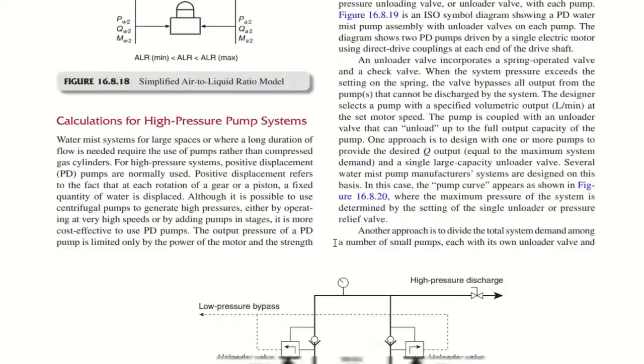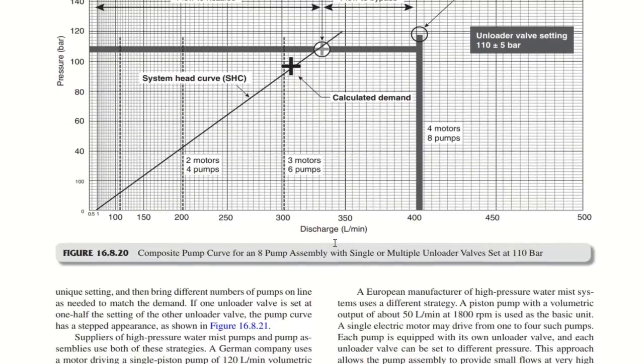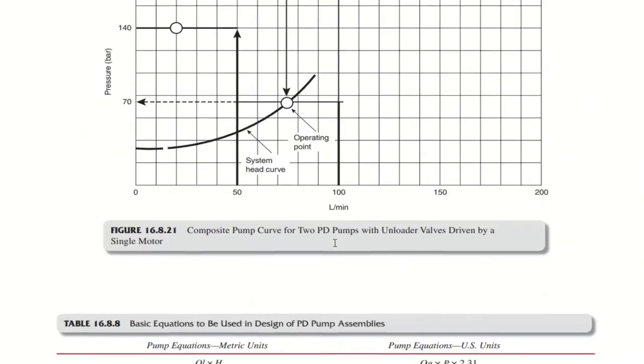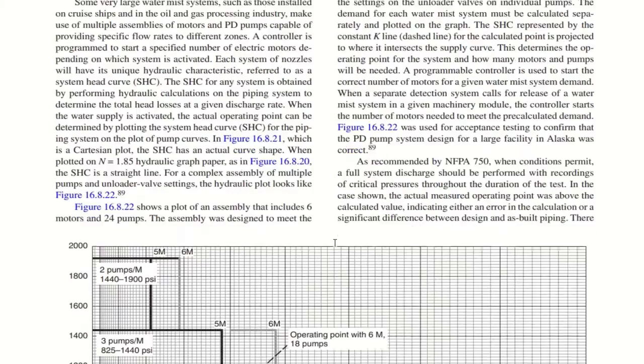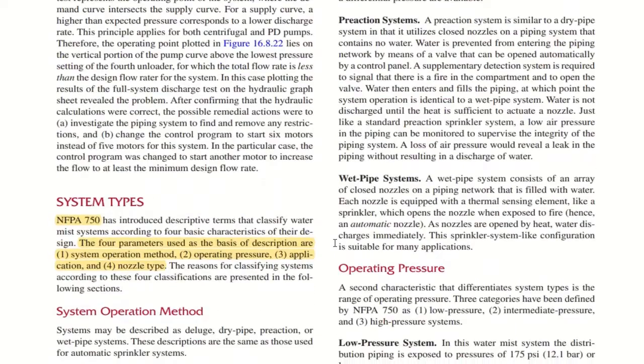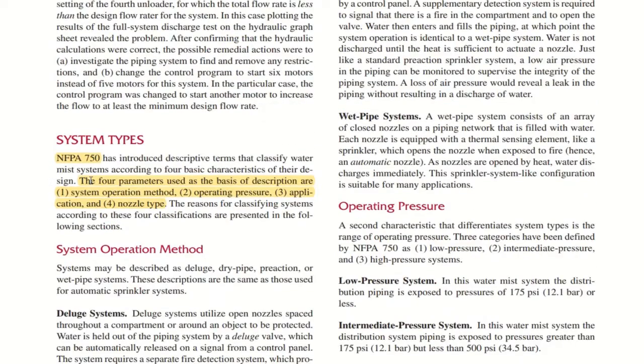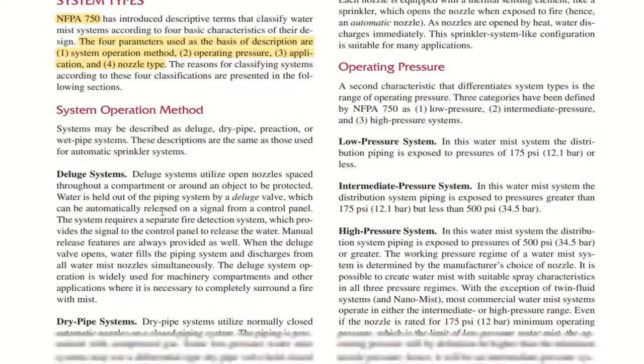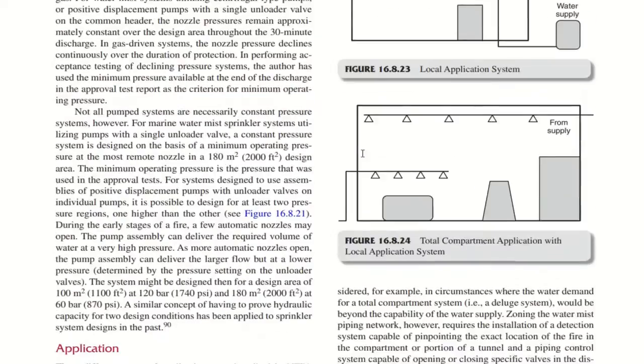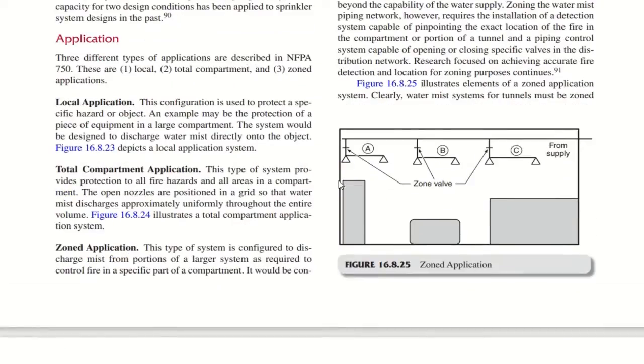So basically this chapter is completely dedicated to water mist systems, or water mist fire suppression systems. So here you have a highlighted point. NFPA 750 introduced some terms. The four parameters used as the basis of description are system operation method, operating pressure, application and nozzle type. These are the four basic characteristics of the water mist system design. So you have the details for this.